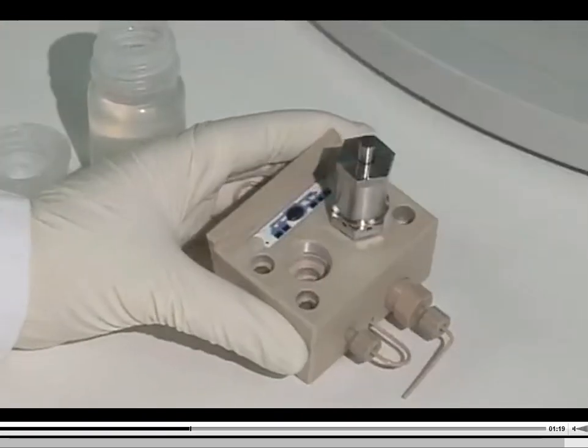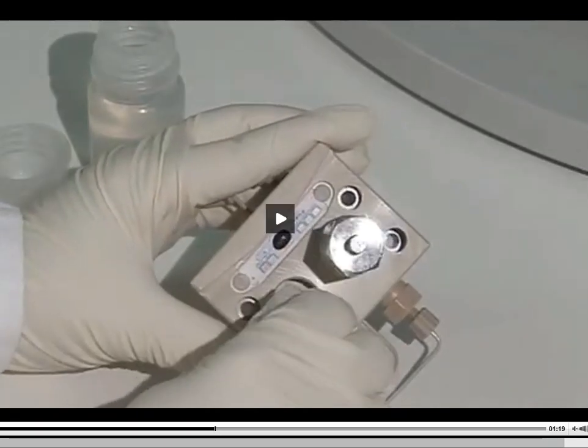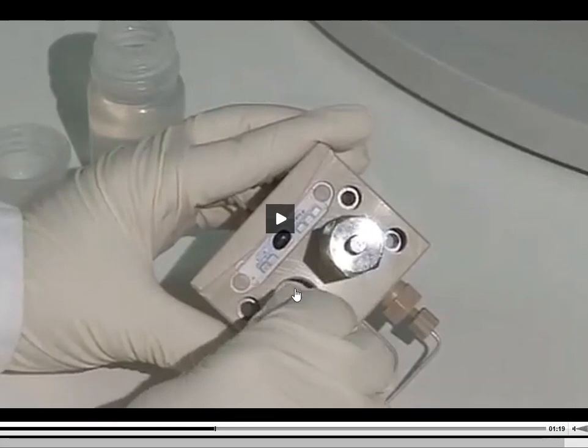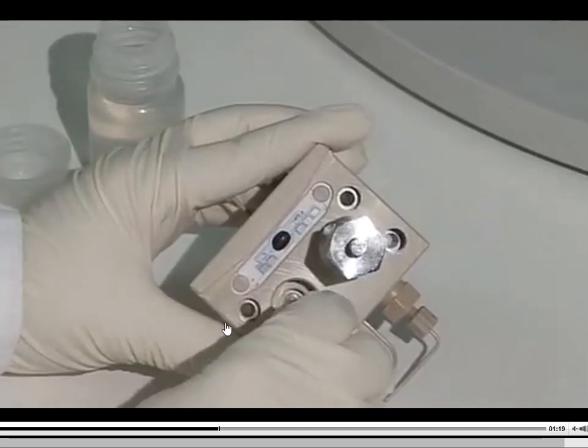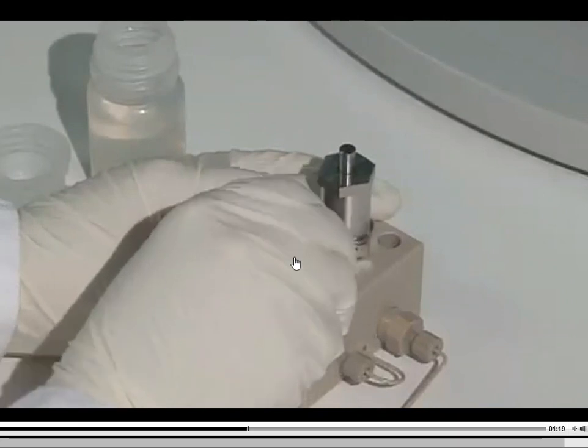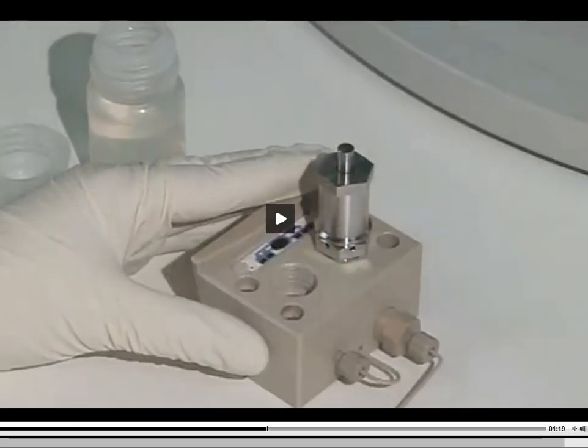The next thing that they're going to do is go through and kind of pop out that holder. This is kind of a guide to take the sample and the piston where it needs to go to. Now what you're seeing is that this person has taken a fancy little tool that Metrohm has given you in your supply kit. You should have one of those around somewhere. And that tool is to go in and basically change these valves. Sometimes you can clean them and sometimes a good healthy rinse with isopropyl alcohol or methanol will do the job, but sometimes they're going to have to be replaced. So that's what you're seeing here - it's the replacement of those little o-rings or seals. That tool gets basically screwed down into where the seal is at, and you just kind of pop it out of there. Right there is your seal at the end of that tube. We're going to trash that one, we're going to throw it away. And now we're going to go get a new seal that we can put down on the inside of that pump.